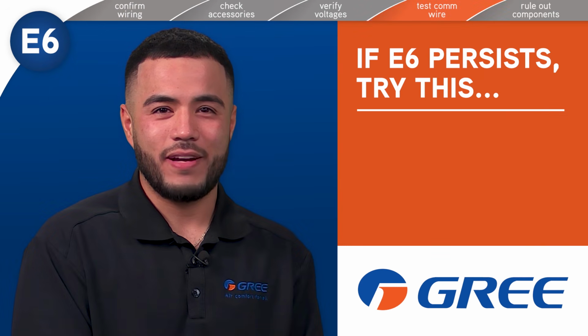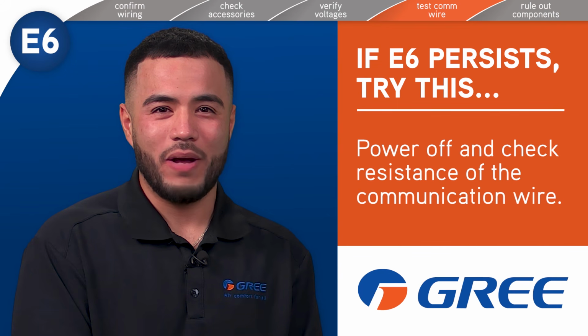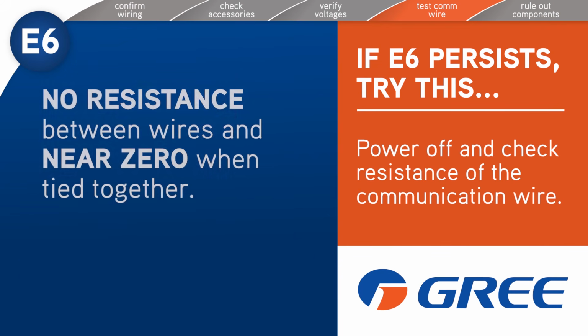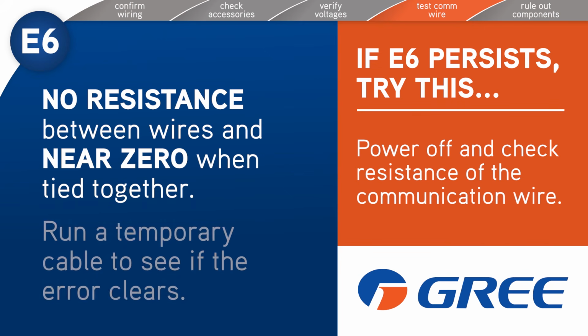If you haven't identified the issue with the previous steps, it's time to power off and ohm out the communication wire. There should be no resistance between wires and near zero resistance when tied together. If in doubt, run a temporary cable to see if the error clears.